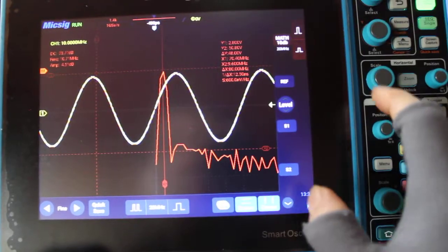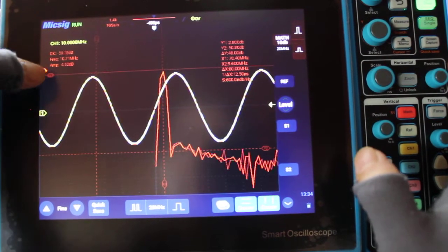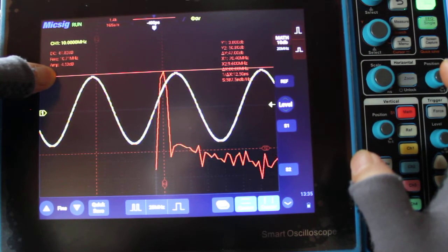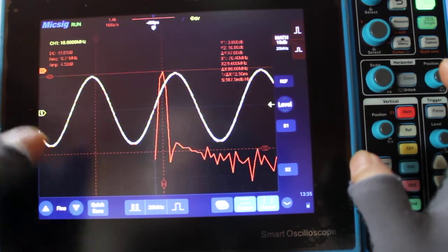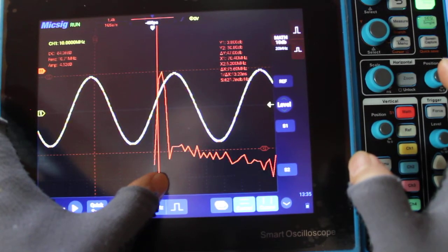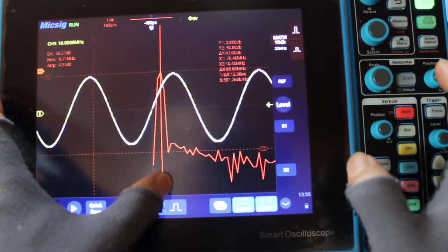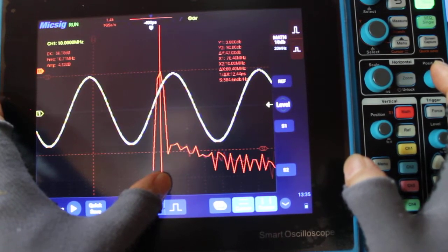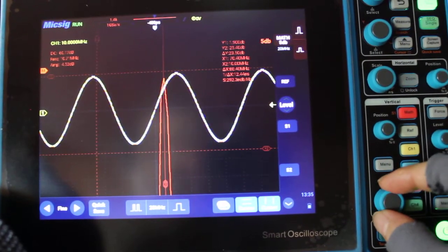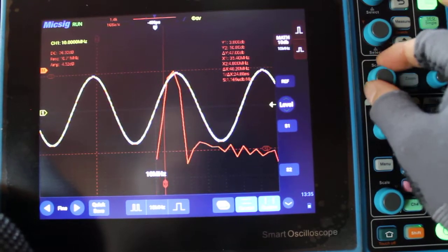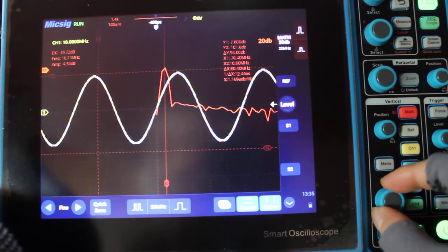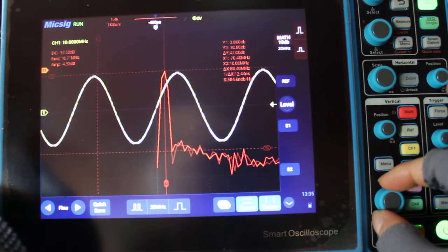And now, just now, click on that. This is the cursor. And the frequency, horizontal is 10 megahertz, and you can also change the time base like that. Sorry, and this horizontal, you can change the horizontal scale, and also the vertical scale. You can adjust it. Now I'm using 10 dB per division.